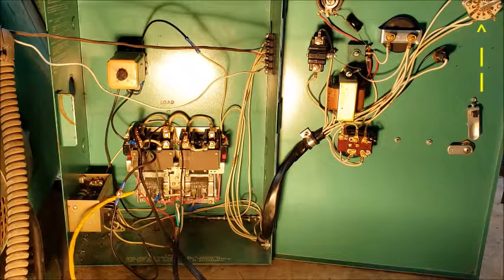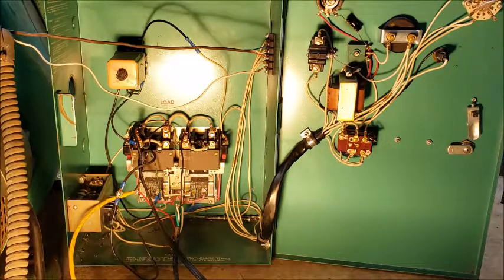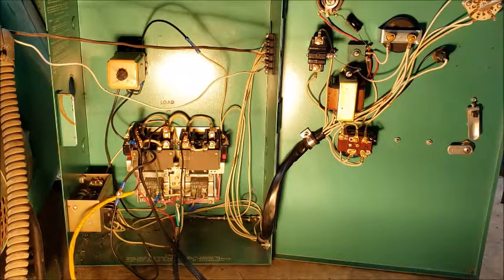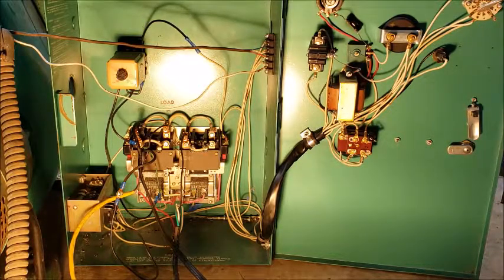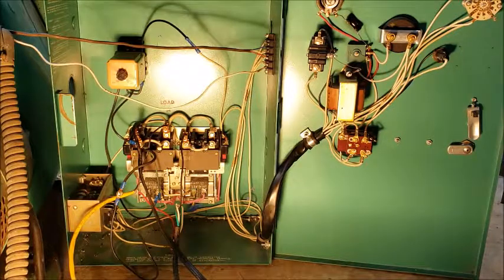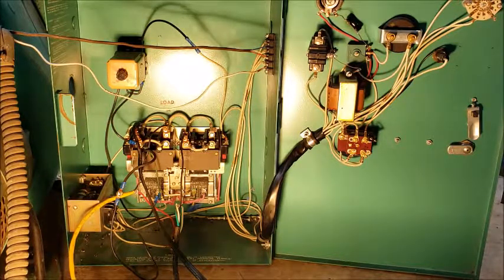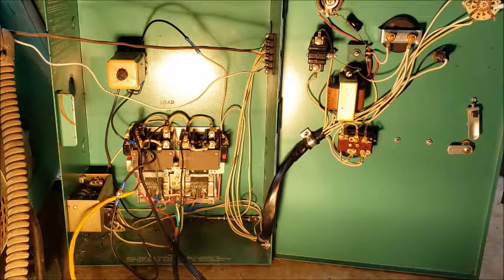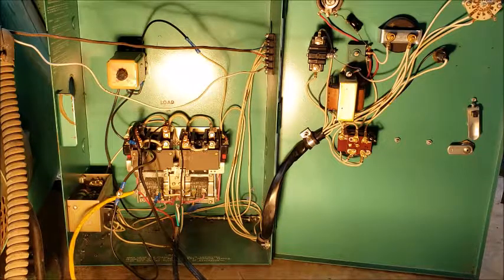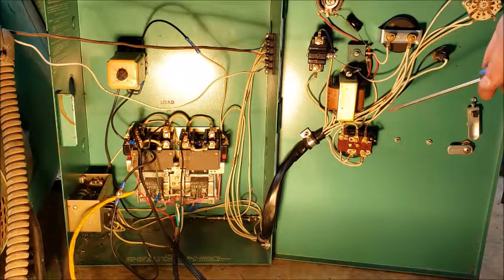This switch switches from auto to stop, and there's a check position that you can switch to check to start the generator while you still have line voltage. And the center terminal of this switch is grounded to this ground lug right down here.